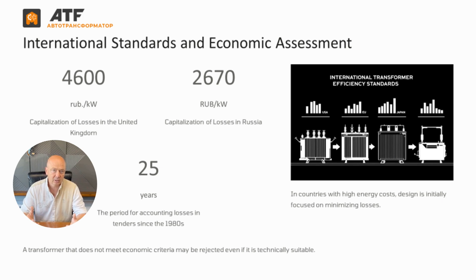This shift was reinforced by international practices. In countries with high electricity prices, like the UK, where the capitalization rate may exceed 4,600 rubles per kilowatt, transformers are designed from the outset with loss reduction as a top priority. In Russia, the rate is currently lower, around 2,670 rubles, but it's expected to rise, making the topic increasingly relevant. Since the 1980s, transformer procurement has changed. Buyers consider not just the unit price, but also the cost of energy losses over a 25-year life cycle. A transformer that fails to meet economic criteria may be rejected, even if it meets technical specifications.